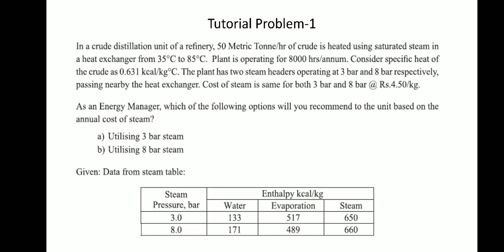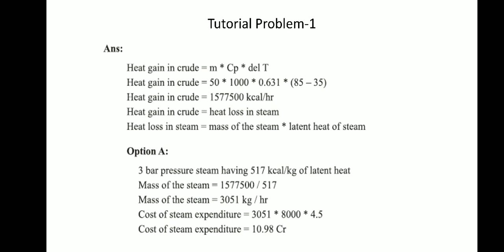Heat gain in crude oil is m Cp ΔT. Cp is the specific heat of crude oil, which is given. ΔT means temperature change. Then we get 1,577,500 kilocalories per hour. Heat gain in crude oil is heat loss in steam, which is the concept of a heat exchanging process. Therefore, heat loss in steam is equal to mass of steam into latent heat of steam. Because here the steam releases heat to the crude oil and the steam is converted to liquid. Therefore, the process is a latent heating or latent cooling process. Therefore, the heat loss in the steam is mass of steam into latent heat of steam.